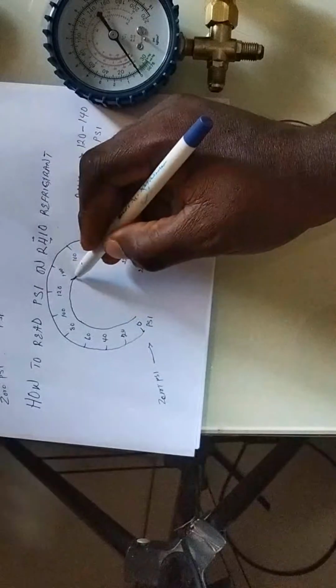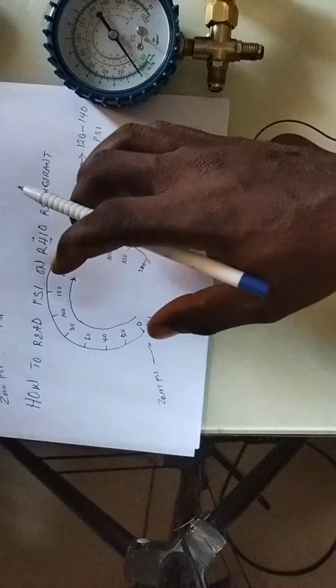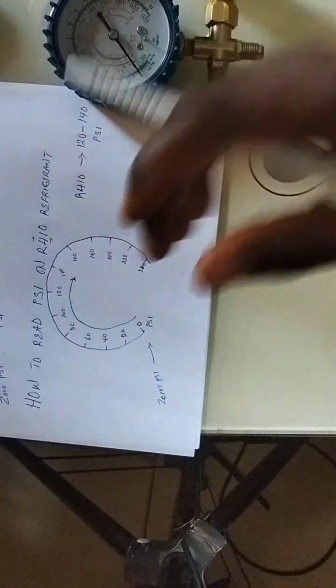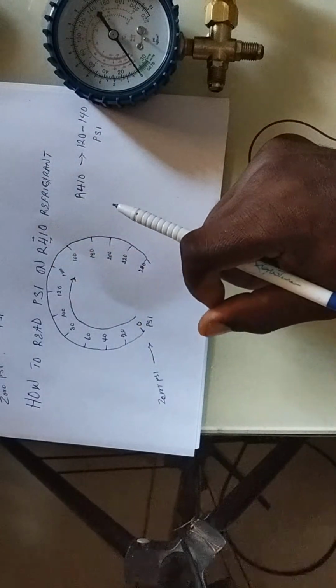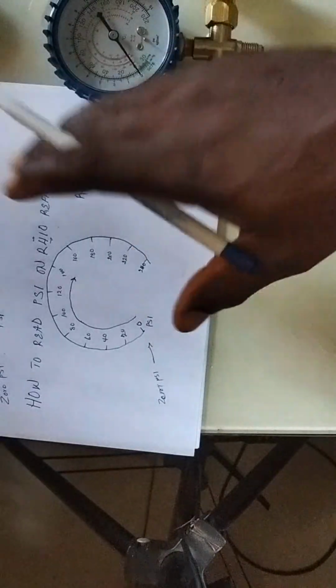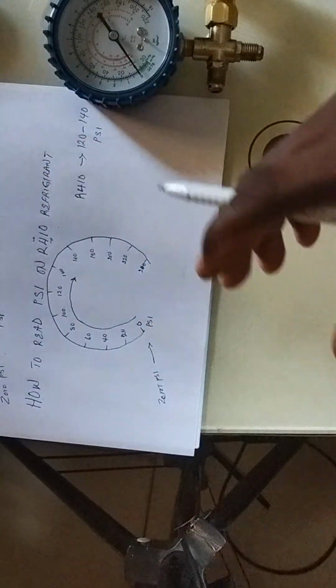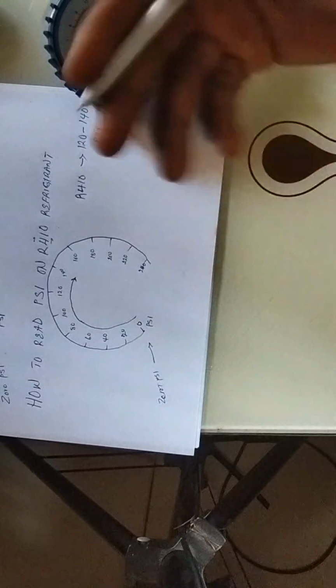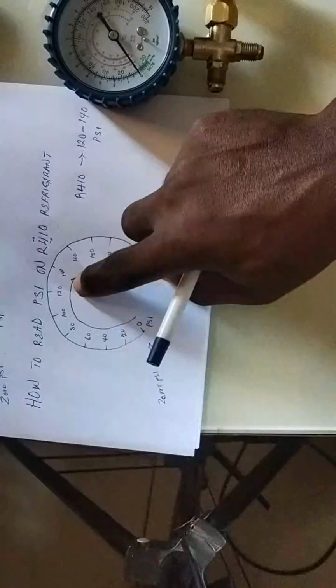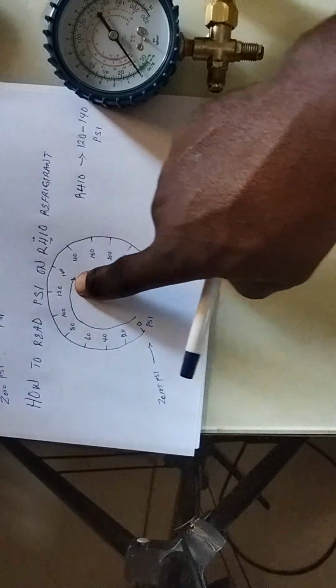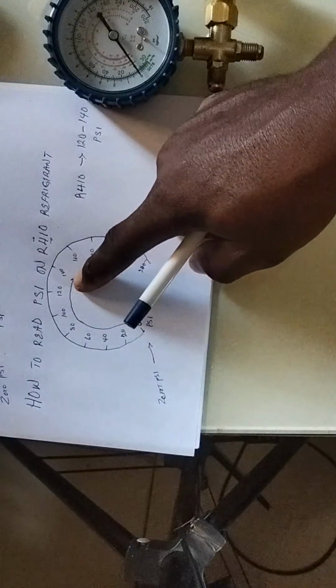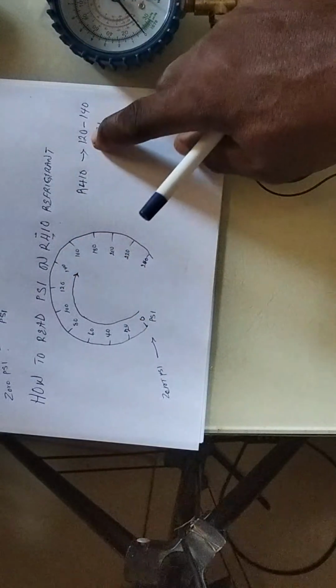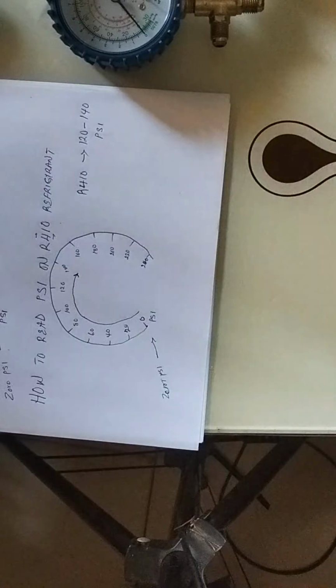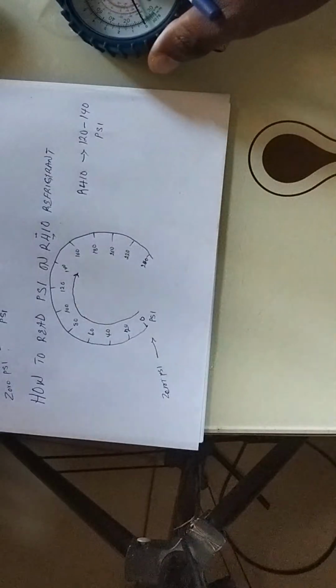Understand? At this point now, you have actually freed up the system, you allow it to work, and it's running for as much as it can run. As far as you don't have any leakage on the system, your air condition is to run for as long as it's good. Understand? And 140 psi is the ideal psi for R410 or R32 refrigerants. Okay, this explanation was for R410.